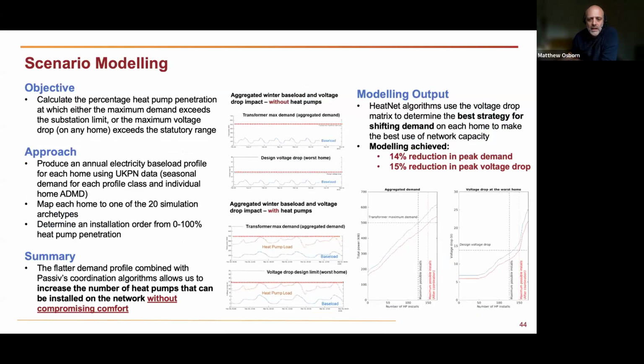To do this, we first produced our annual baseload using UKPN's own planning tools—that's the graphic in the top center—and then mapped this back to our 20 households. We then set a sequence of installing increasing numbers of heat pumps onto our network, from 0 now up to 172 properties, or 100%. We found that if we distributed those heat pumps at random, we hit voltage drop statutory limits before we hit substation capacity limits, particularly on this network.